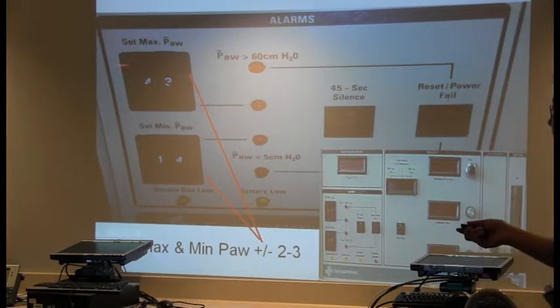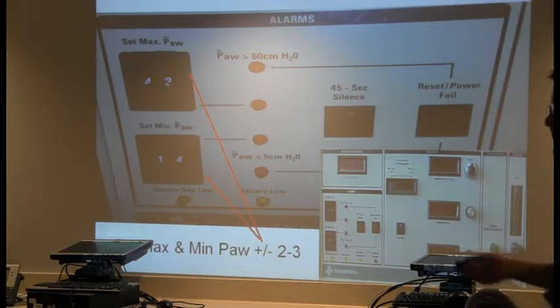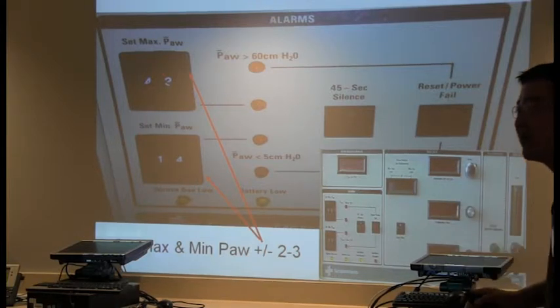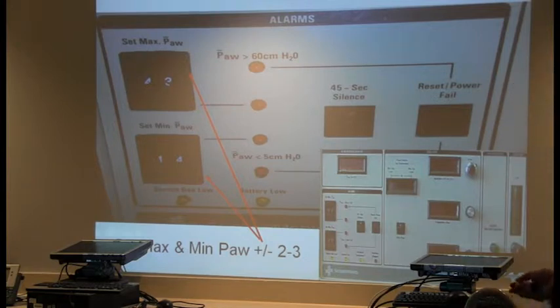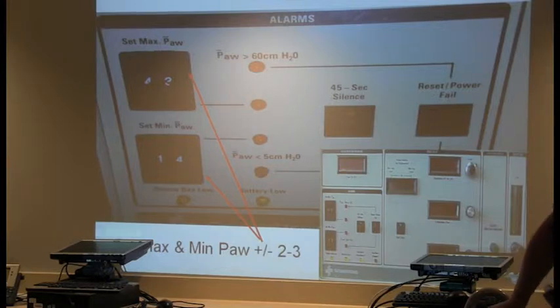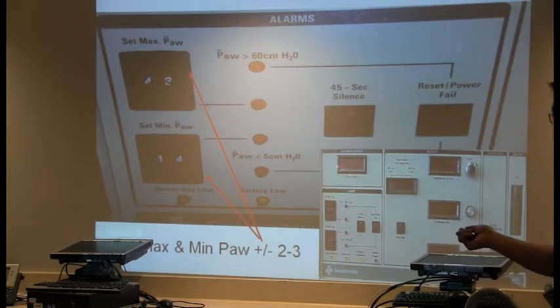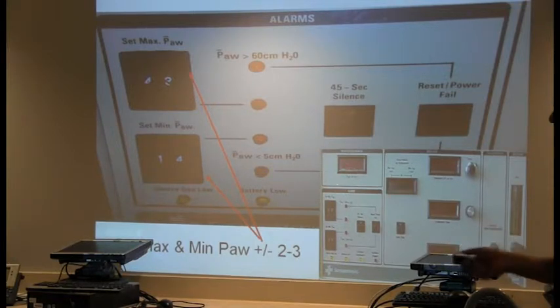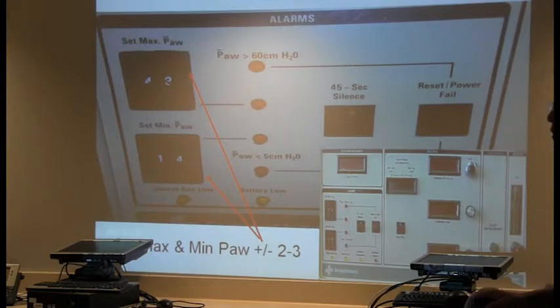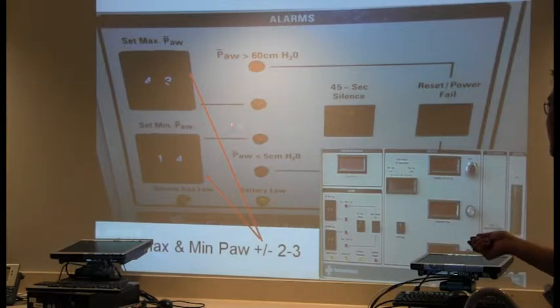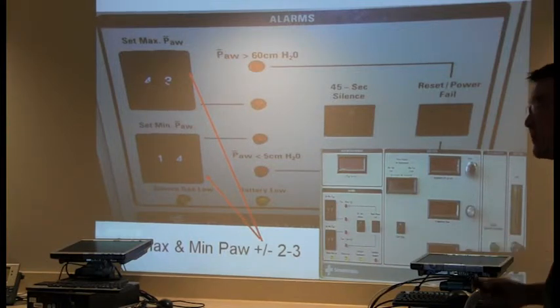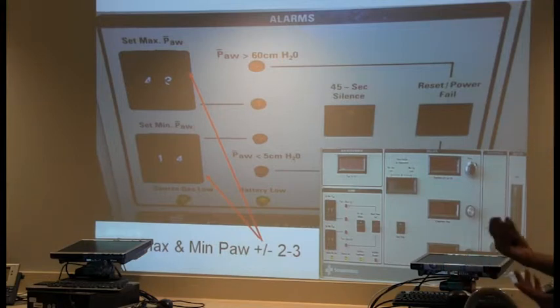This happened during some of the competencies I performed, and like I said, you guys did a really good job, but these are fine details, and it's amazing how these little fine details affect the oscillator, because it's a safety mechanism. They don't want you to have this huge of a variance. That's why some people max out their above and below alarms, because they think they're helping themselves, and actually they're initiating a problem. So your mean here says 25. Like I said, keep it 2 to 3 above, and don't go above 20% of it. Otherwise you'll get this, where it's less than 5, because the pressure difference is so huge that your vent won't start.